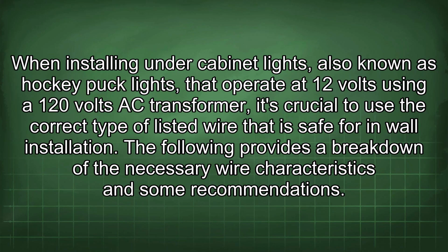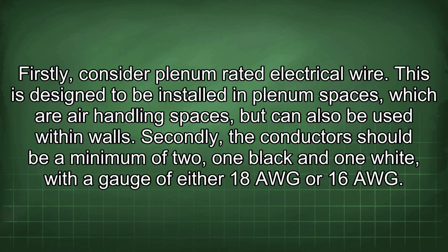When installing under-cabinet lights, also known as hockey puck lights, that operate at 12 volts using a 120 volts AC transformer, it's crucial to use the correct type of listed wire that is safe for in-wall installation. The following provides a breakdown of the necessary wire characteristics and some recommendations. Firstly, consider plenum-rated electrical wire. This is designed to be installed in plenum spaces, which are air-handling spaces, but can also be used within walls.